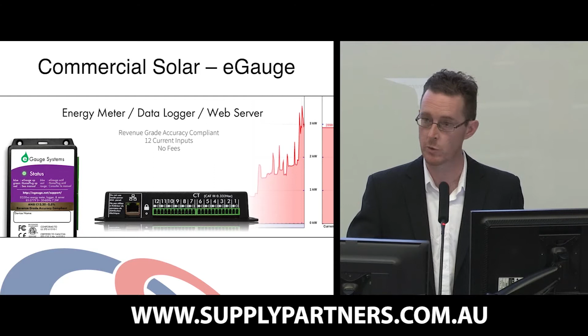A very quick comment on clip lock. I mention this because I've seen people come unstuck on it. We offer clip lock clamps from Clenergy. They have a single clamp that suits 4 different roof profiles, so for any of the 4 profiles, that clamp is perfectly acceptable and engineered for use, but the profiles themselves have very different numbers of connection points or attachment points required.